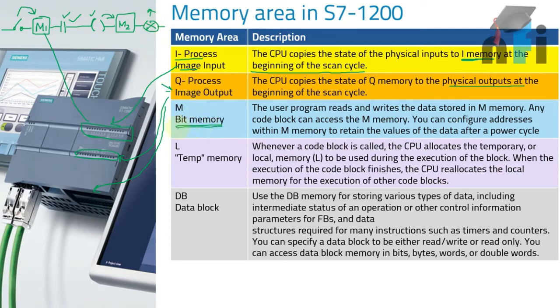Then you have bit memory. We have some special memory in our PLC — one is general bit memory, one is specialized bit memory. Specialized bit memory has special functions; for example, you have internal clocks in the PLC which will turn on and off at their own interval, and you can use these internal clocks in your logic. General memory is used for latching, making timer circuits — you can use normal bit memories for that as well.